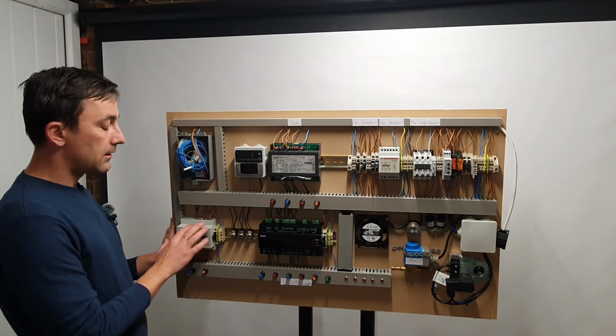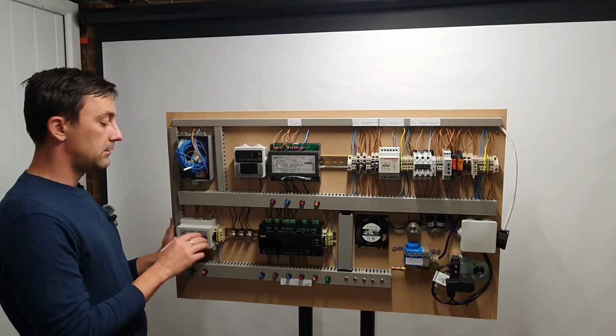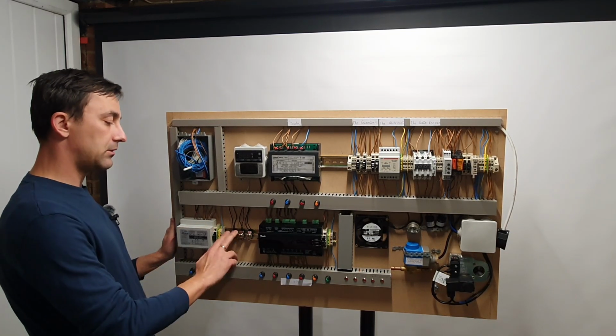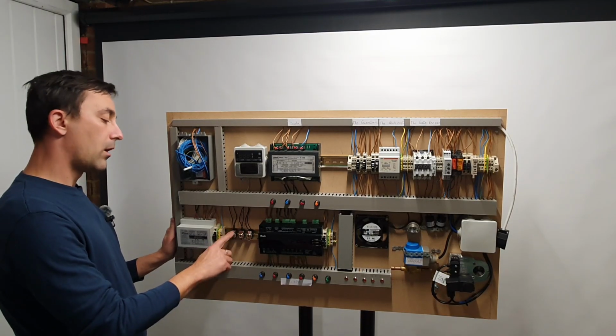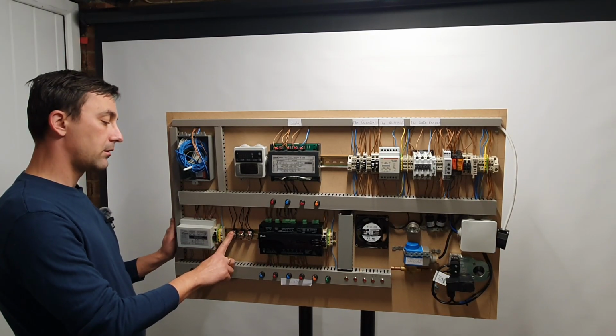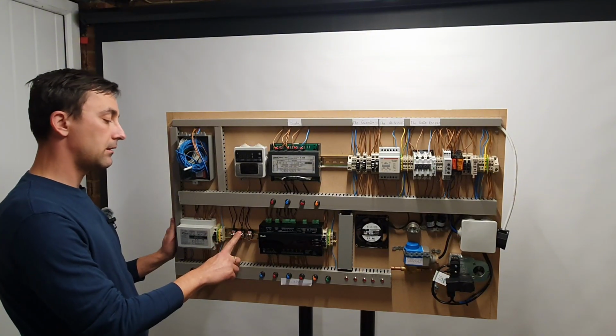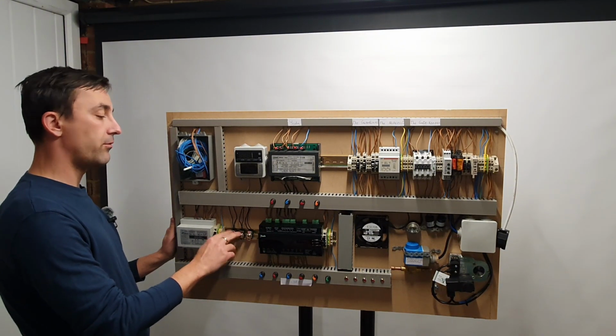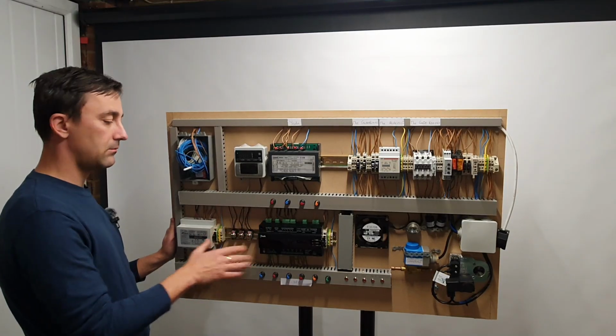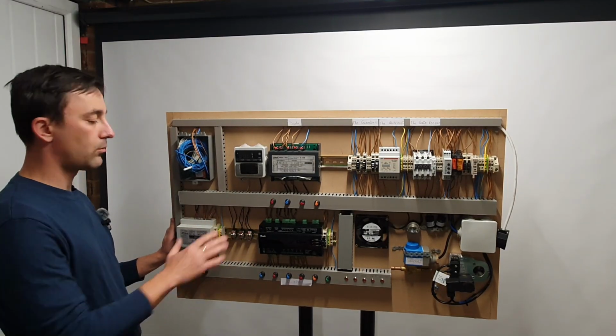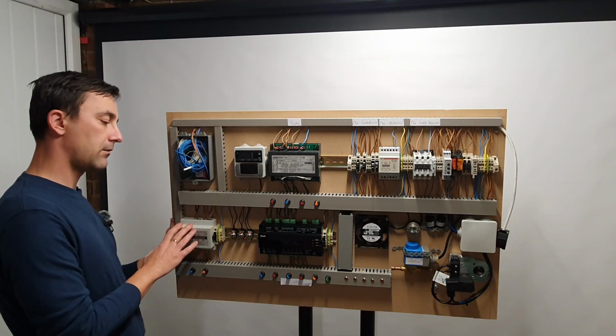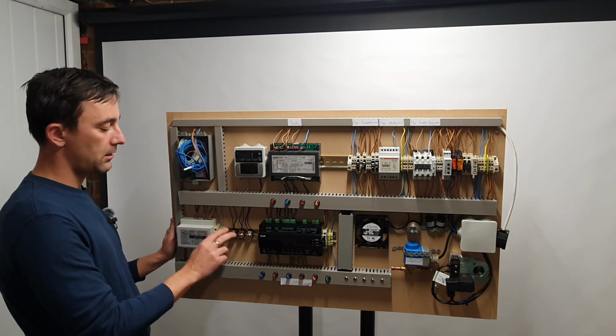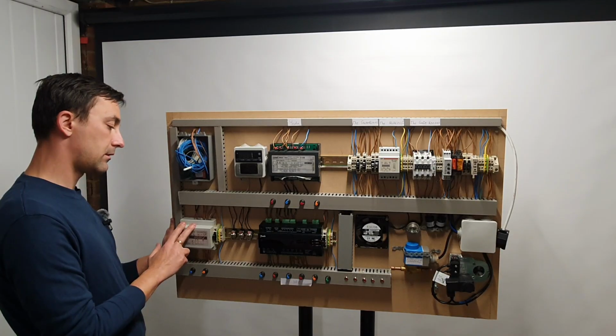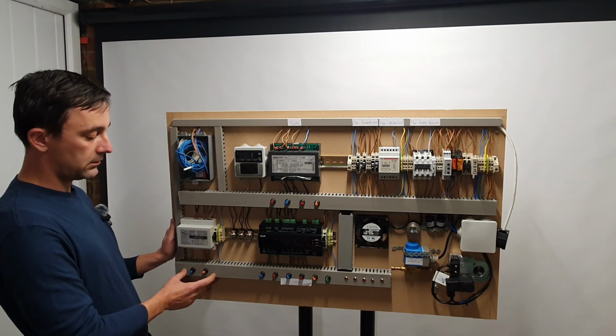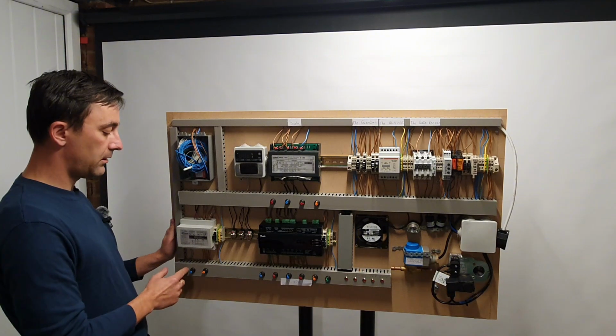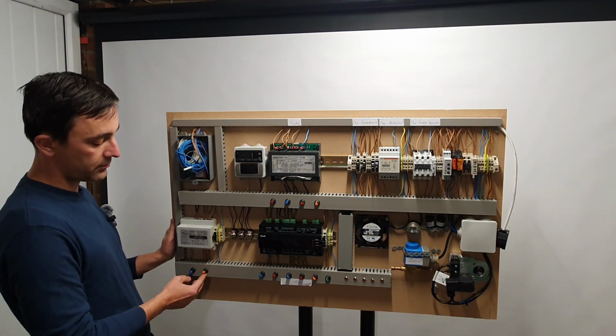However, I tried to fit two switches, one for a cold room door and one for the safety circuit, and I tried to make both of them work with these two controllers. I couldn't because they're a bit different. So one is low voltage, one is high voltage. So these two switches are linked to this controller and these two temperature probes. This would be our air-on and this would be our defrost probe.